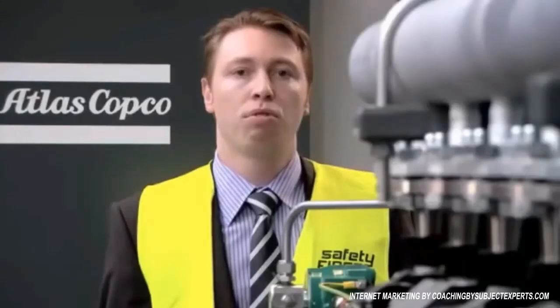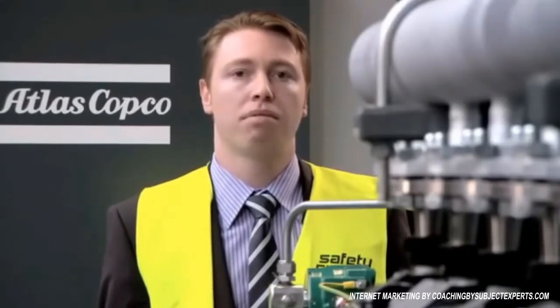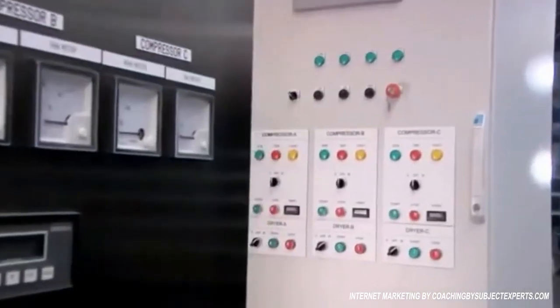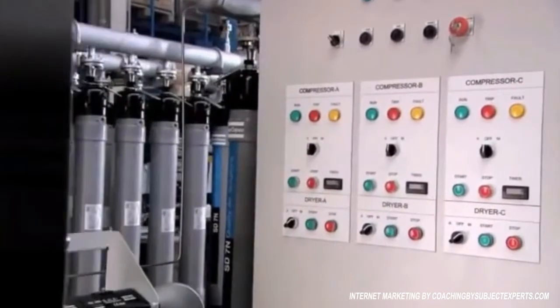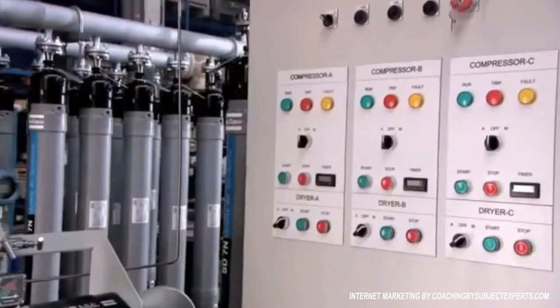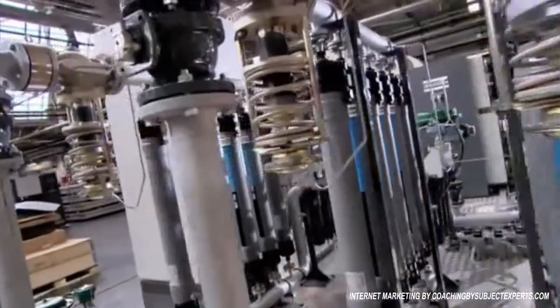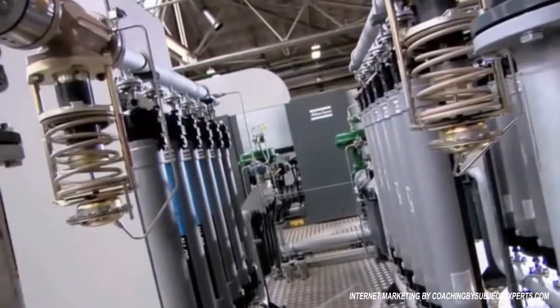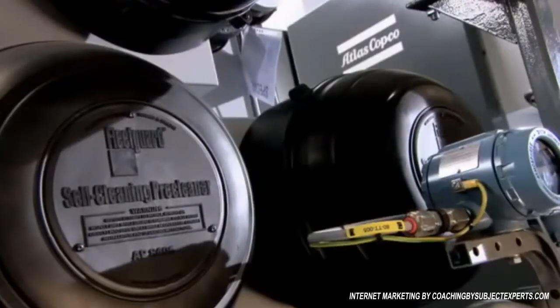Because of the remote location, the availability and reliability of instrument air is paramount. The standalone PLC will regulate the redundancy in terms of processing and power supply. Due to the high ambient conditions and the remote location, membrane dryers have been used. This was done because dew point suppression and ease of maintenance was requested. The use of cyclone filters for pre-filtration in a dusty environment increases the reliability of the compressor.